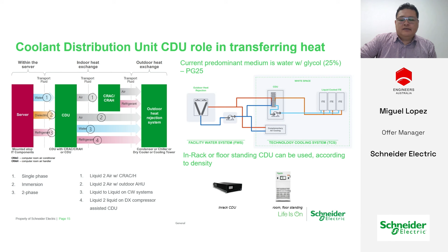Liquid-to-liquid CDUs are the ones that will give up heat from the technical loop to the facility water, and this facility water will then be taken out to some means of outdoor heat rejection, either an existing chilled water loop, a dry cooler, or an open cooling tower. So this is a good little explanation of how the hydraulic system works, which you may wish to inspect more closely at your leisure. The takeaway message from this slide is that you have rack-mounted CDUs, depending on the heat rejection needs of your server, of your rack. A smaller rack-mounted CDU could suffice, but for the larger applications, a floor-standing CDU is probably the way to go. Moving on to the next slide.